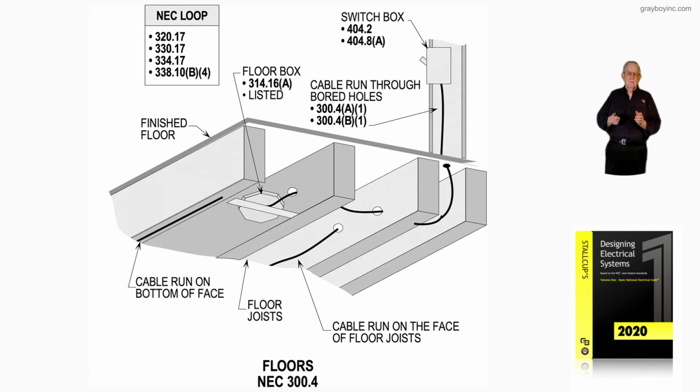Now, any kind of service entrance cable that comes through the surface of the floor has to be protected up to about 6 inches. However, if you looked at a city ordinance, state or county, they may require you to protect it up to the wall to where you terminate it to a switch. But here, we're inside the wall area on the side of this stud, so it's considered protected. But notice we're not looking at support rules here.